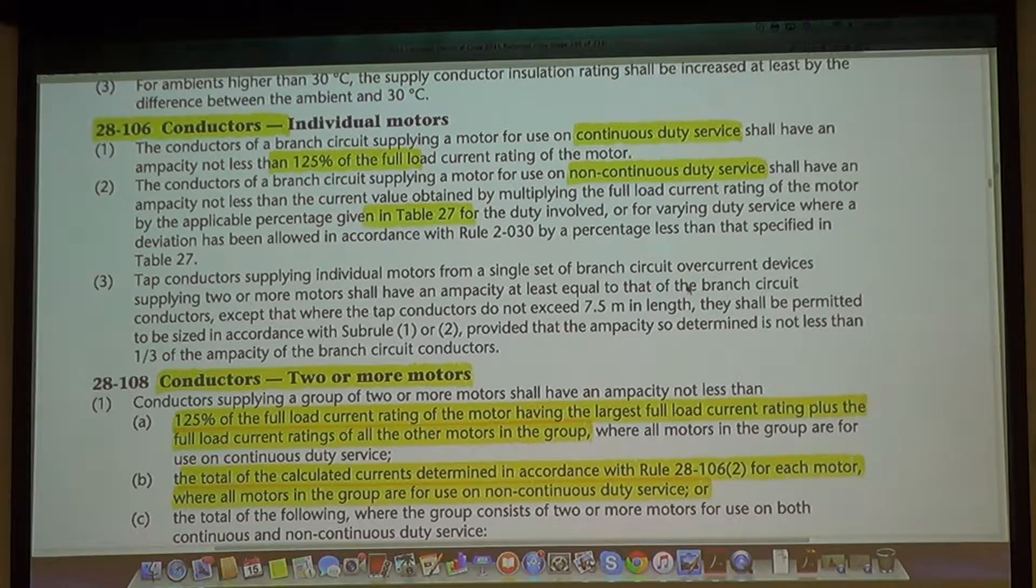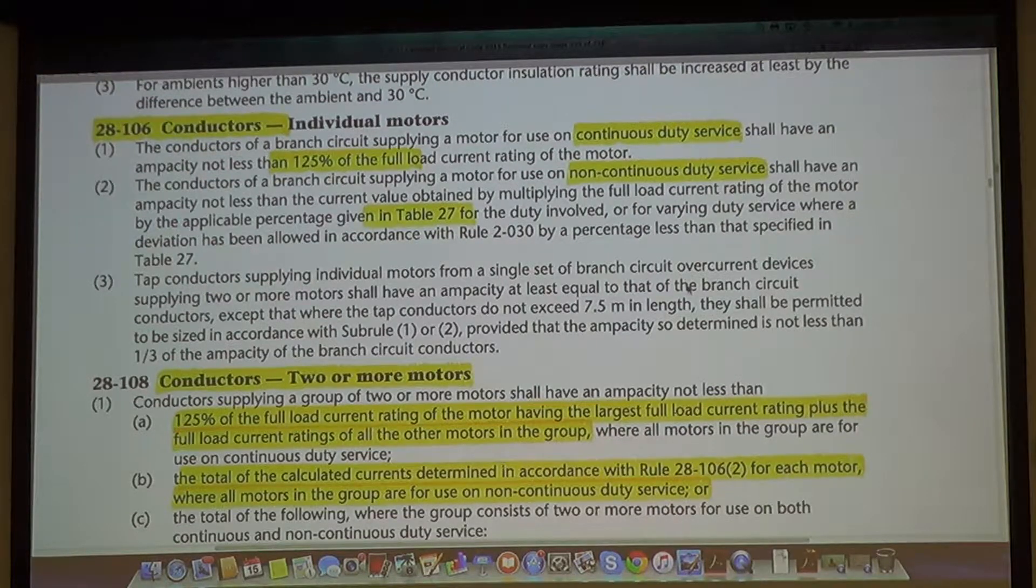What is a continuous duty? Any motor that is turned on for more than 50% of the time. A non-continuous duty would be a motor that turns on and off on a recurrent basis.